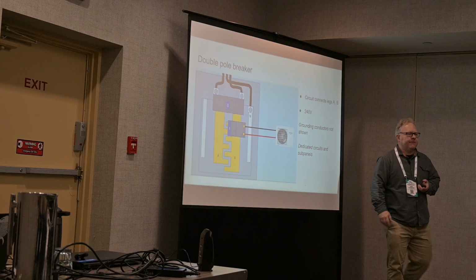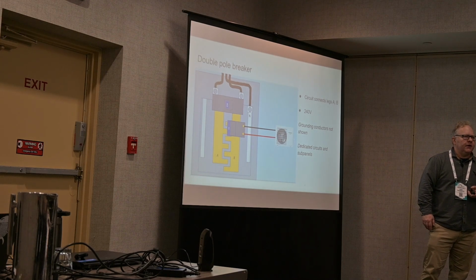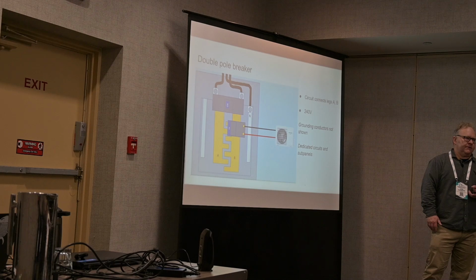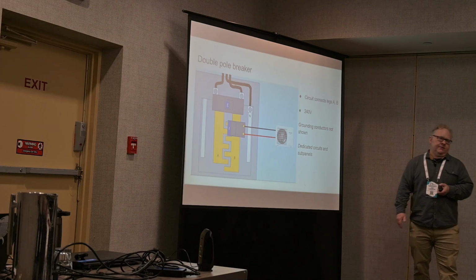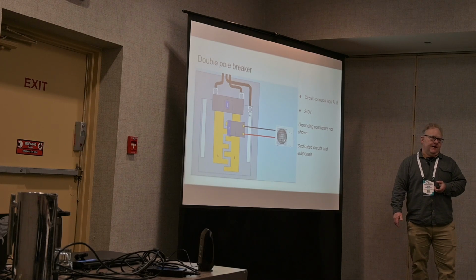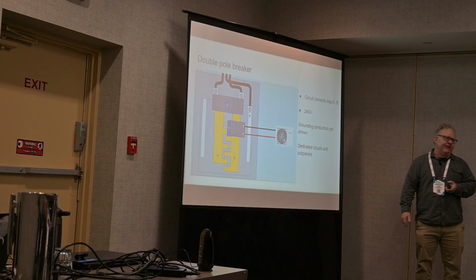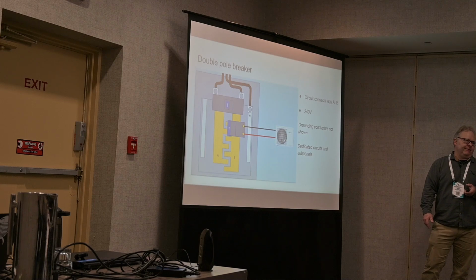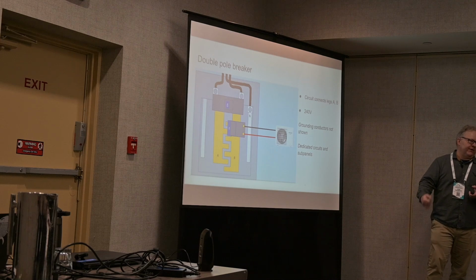Yeah, Jamie. Hey, John. Sorry if you're taking questions at the end. No, go ahead. When it comes to grounding, I've had electricians I've sent out, and they need to charge for putting spikes in the ground outside to ground the system. If they're not already there, how's it grounded typically? Just hope for the best, or usually water line? Water line? Yeah, there needs to be a central ground in the system, and I think by code now it has to be a rod that's driven deep into the ground.